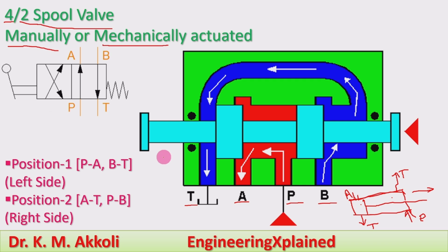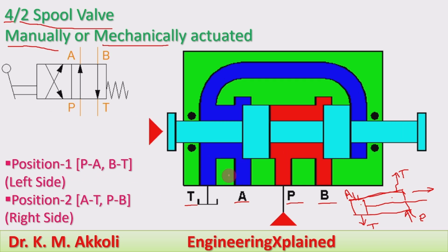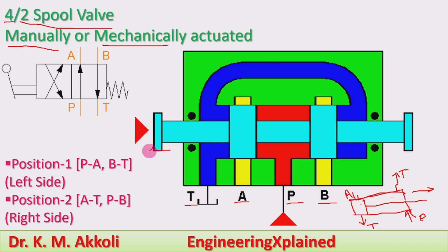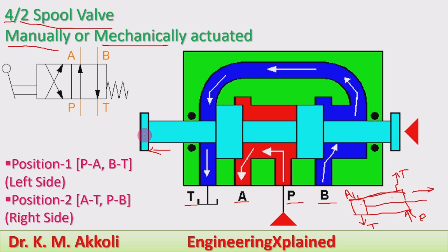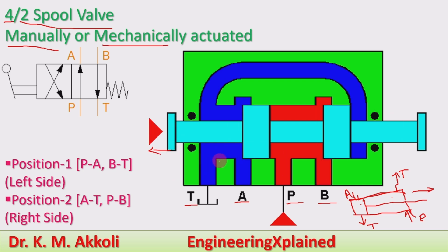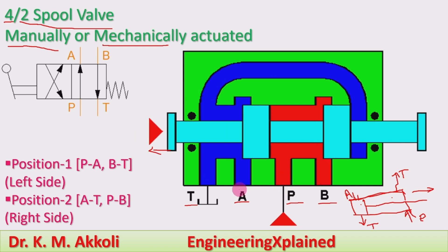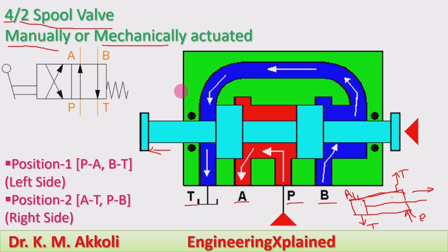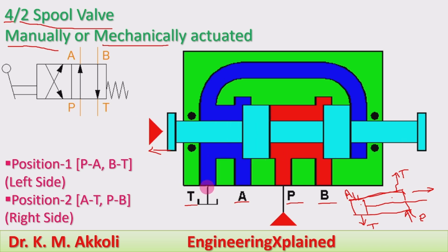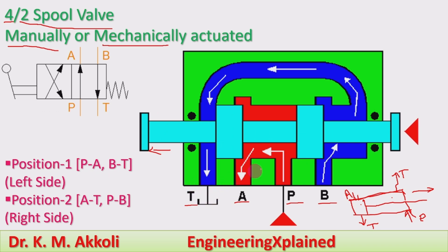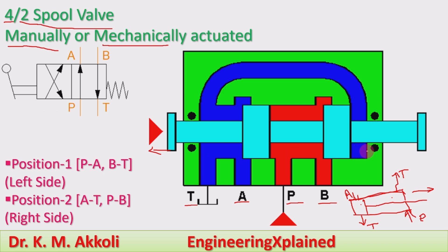Now let us look at the two positions. Position one is the left side. When the spool is in the left-hand position, it is called position one. During that time, the pump port (P) is connected to the actuator port (A), and the back port (B) is connected to the tank (T) — so P to A and B to T.